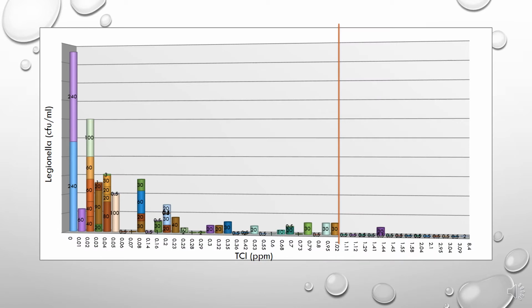So this is here just to remind everybody what we discovered that first summer when we first found out we had Legionella here on campus in higher quantities than safe. Just a reminder that when we get to about 1 part per million total chlorine, we saw a significant decrease in the amount of Legionella in our cooling towers.